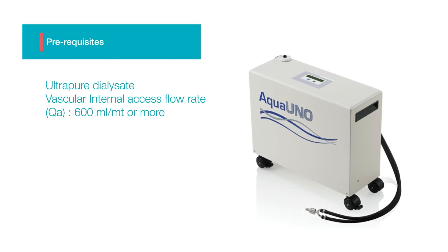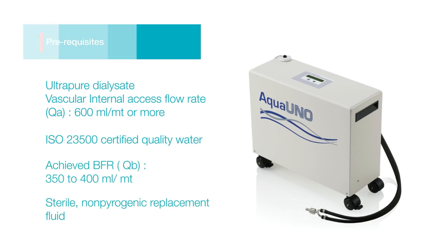As for the prerequisites, we need ultra-pure dialysate, vascular access internal flow rate of 600 millilitres per minute or more, ISO 23500 certified quality water, achieved BFR of 350 to 400 millilitres per minute, and sterile non-pyrogenic replacement fluid.